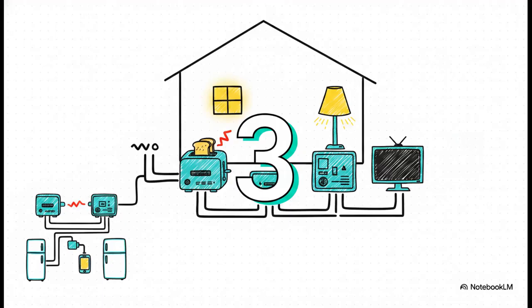But there is a catch to how we deploy these life-saving RCDs, and it's beautifully represented by the number 3. Under the NZS 3000 residential rules, 3 is the maximum number of final subcircuits that can be protected by any single RCD. Why 3? Well, we go right back to minimizing inconvenience. If a faulty toaster trips an RCD, and that one RCD was guarding your whole house, you'd plunge the entire place into darkness. By limiting it to a max of 3 circuits per RCD and requiring at least 2 RCDs per house, a single fault stays totally contained while the rest of your fortress stays illuminated.